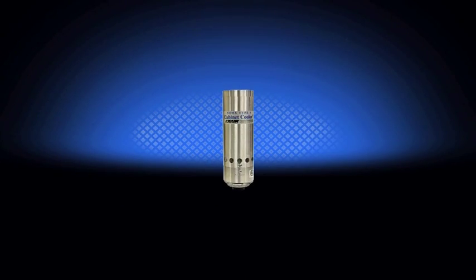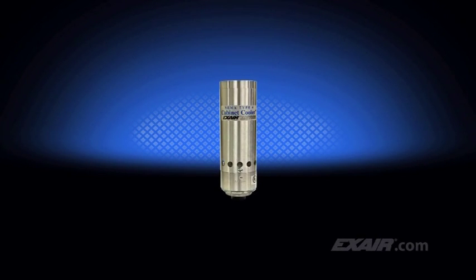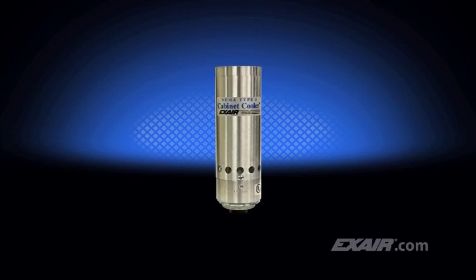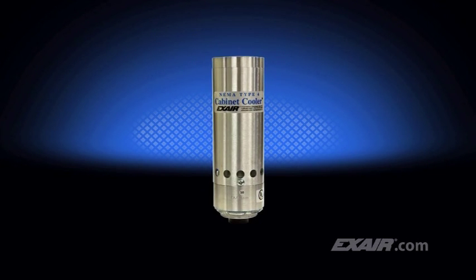EXAIR cabinet coolers are a low-cost, reliable way to cool and purge electronic control panels with cold air. Cabinet coolers incorporate a vortex tube to produce cold air from compressed air. There are no filters to clog, no CFCs or refrigerant to leak out, no compressor to fail, and best of all, no moving parts to wear out.